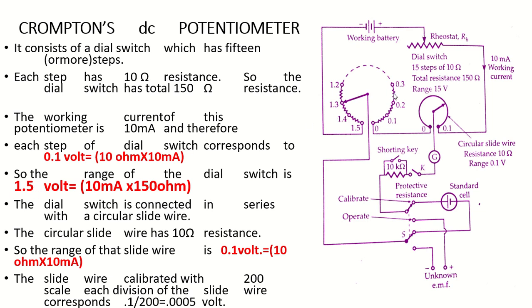This large dial switch is connected in series with a circular slide wire. This small circular slide wire has a total resistance of 10 ohm. So the total voltage across the slide wire is 10 ohm × 10 milliampere = 0.1 volt. Therefore, the total range of this small slide wire is 0.1 volt, while the range of the large dial switch is 1.5 volt.